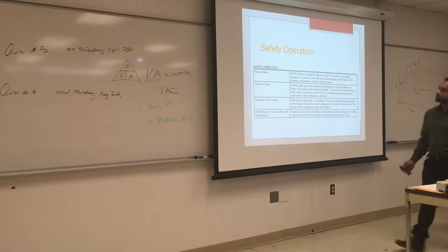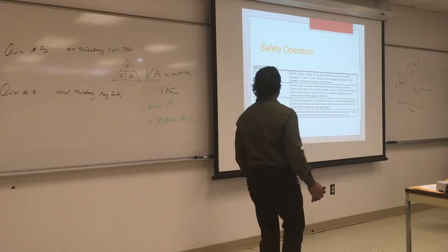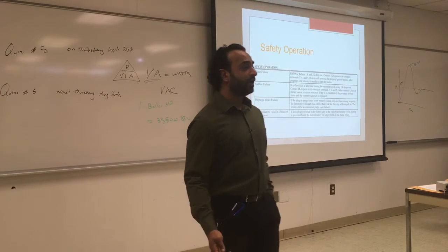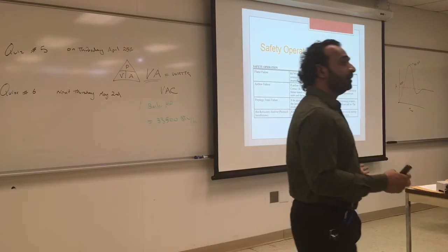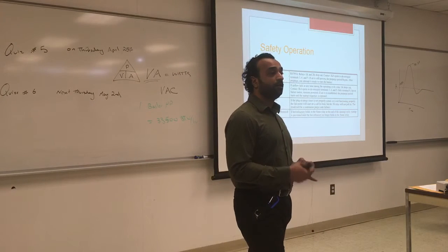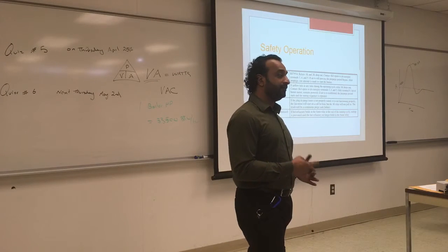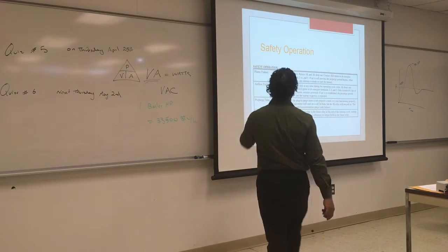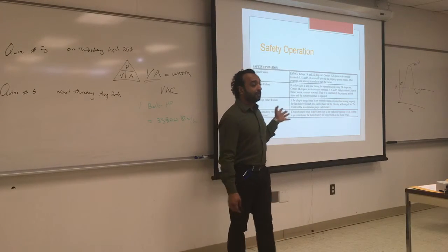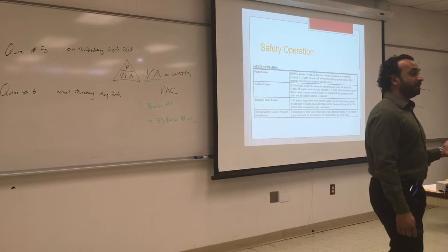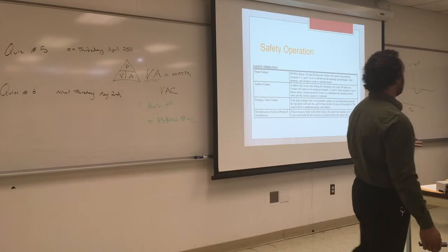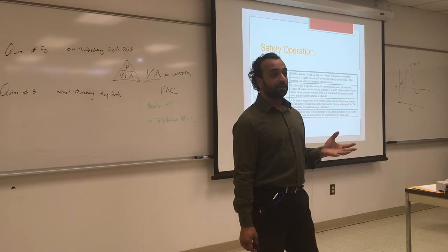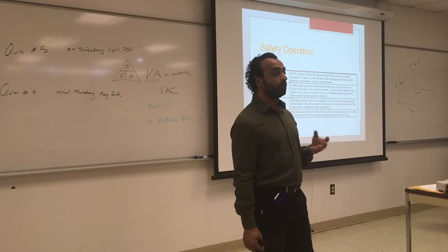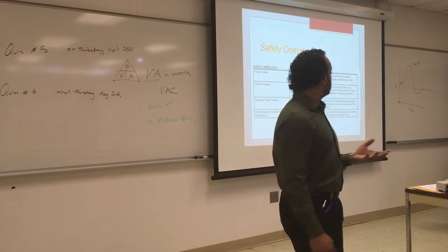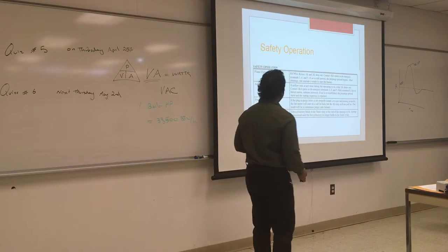Safety operation. So for flame failure, what would happen if anything fails? We can check what happens if anything goes wrong in the operation. Of course, we have airflow switches. We have pilot failure. We have flame failure. So we want to check what's happening with the flame failure. What kind of alarm do we get? Those things will not give you a lot of indication of what's wrong. Some more advanced controls will give you signals and codes to know which component failed. So flame failure, this is what will happen.